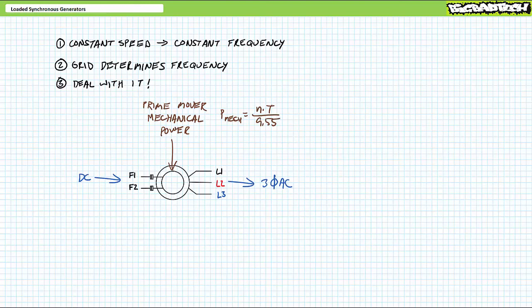On a very basic level, changes in real electrical power output necessitate changes in rotating mechanical power input. Consider a real-world prime mover and generator working in isolation in the unloaded state. Two important observations can be made about this isolated and unloaded state. One, given the generator is working in isolation and not synchronized to any other larger grid, the prime mover rotational speed is the single determining factor of output frequency. Two, given the generator is presently unloaded, no mechanical power is being converted to electrical power, so any oppositional torque experienced by the prime mover is purely to overcome friction.